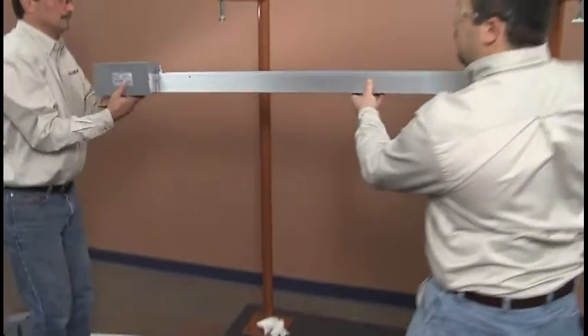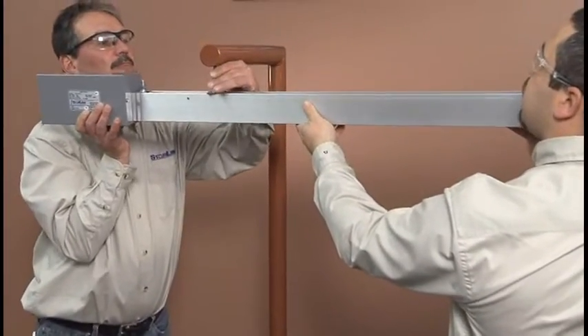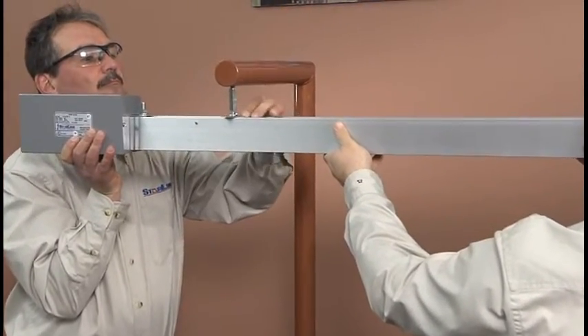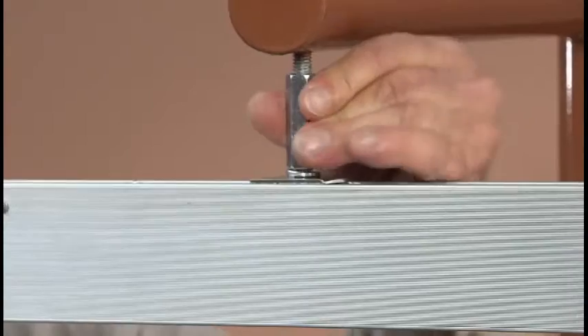Then insert the hanger bolts at 10 foot maximum intervals. Orient the striped side of the busway to align properly with the power feed. Then secure this section to the busway supports.